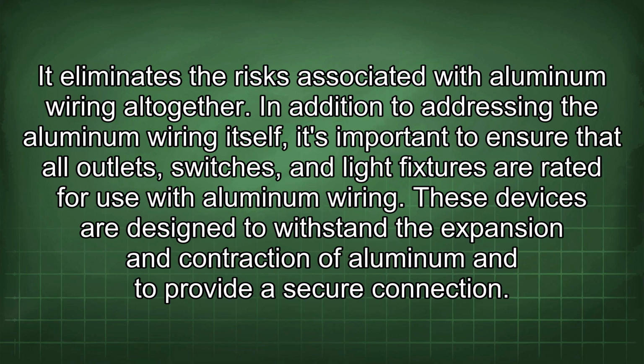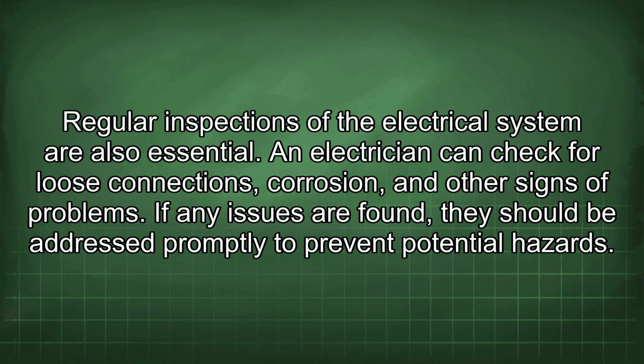In addition to addressing the aluminum wiring itself, it's important to ensure that all outlets, switches, and light fixtures are rated for use with aluminum wiring. These devices are designed to withstand the expansion and contraction of aluminum and to provide a secure connection. Regular inspections of the electrical system are also essential. An electrician can check for loose connections, corrosion, and other signs of problems. If any issues are found, they should be addressed promptly to prevent potential hazards.